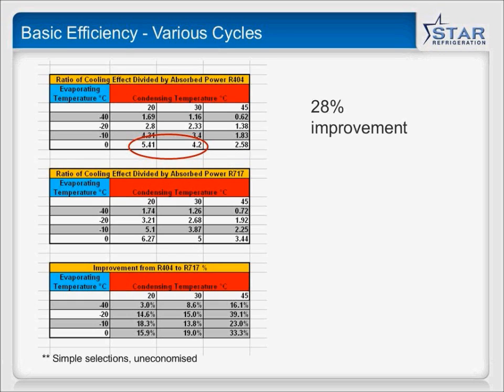28% improvement just by helping the condenser, by making sure it's clean, maybe having the right sort of valves and the control philosophy for that. What if we changed refrigerant though and did that? We see a 49% improvement from 4.2 up to 6.27 just by changing the numbers and the gas. Now obviously you can't take an existing system, take one gas out and put a different gas of a completely different family type, but you've got to bear in mind that only 15% of the life cycle cost of refrigeration equipment is the capital cost. The vast bulk of it is 70%.